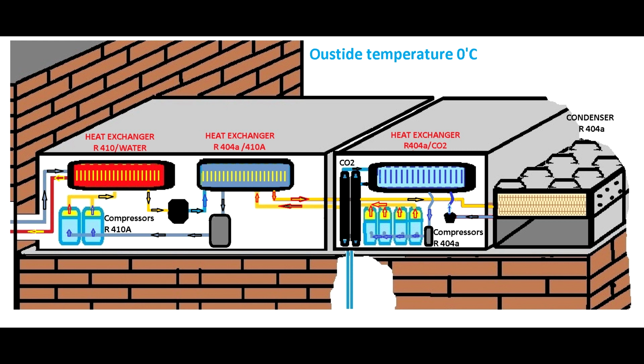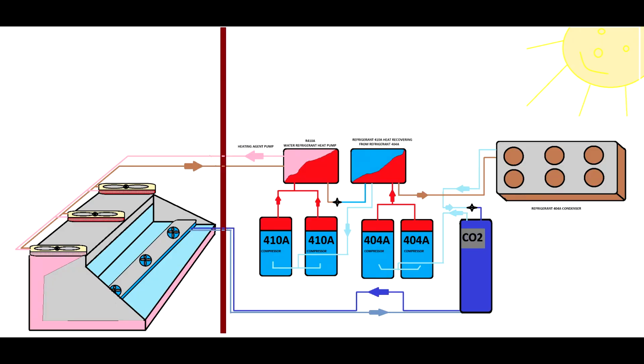So if you look, we have a heat exchanger 410A, which is water and refrigerant. The second one is 410A to 404. Now if you look, if you have a very hot summer, the heat exchanger isn't working because the store is already hot - outside is very hot and the store is naturally heated because of the hot weather outside. Under such conditions, the condenser will eliminate the absorbed heat.